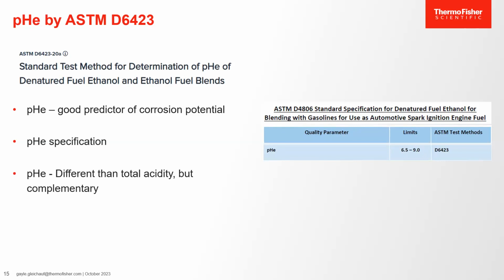pHe is different than total acidity because total acidity does not measure activity of the hydrogen ions. Total acidity overestimates the contribution of weak acids, such as carbonic acid, and can underestimate the corrosion potential of low concentrations of strong acids, such as sulfuric acid. The two measurements both provide useful but different information, and they complement each other.